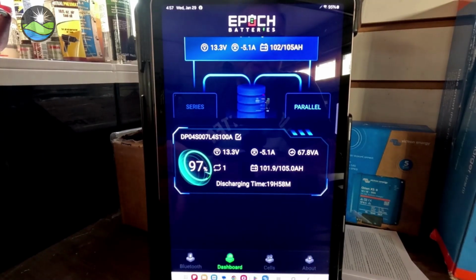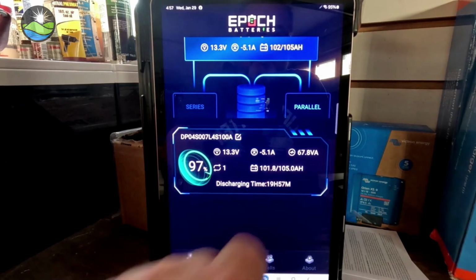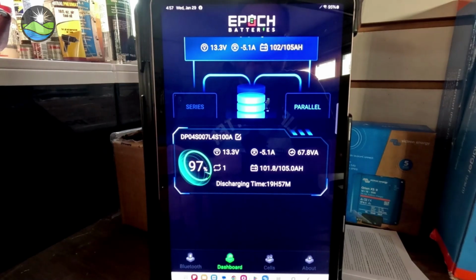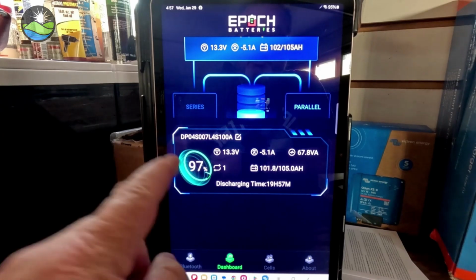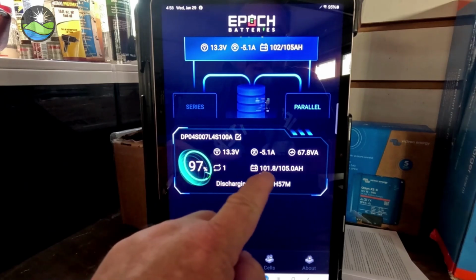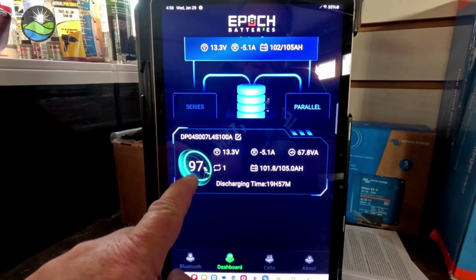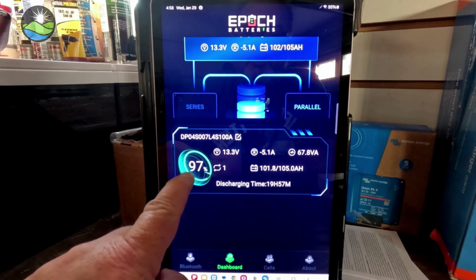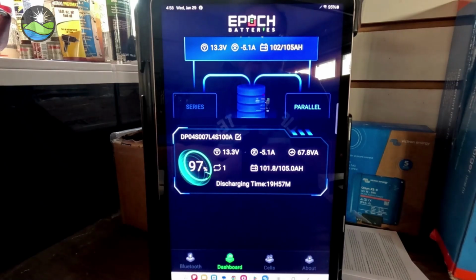And over here you can see that number bouncing around a little bit. 67.8 watts, so 13.3 times 5.1 is roughly 67 watts. And this number right here will start to go down, and this number will start to go down, and that's calculated by how many amps we're using over time. So this 97% and this as well, these are the state of charge. Okay, these can get out of sync over time.